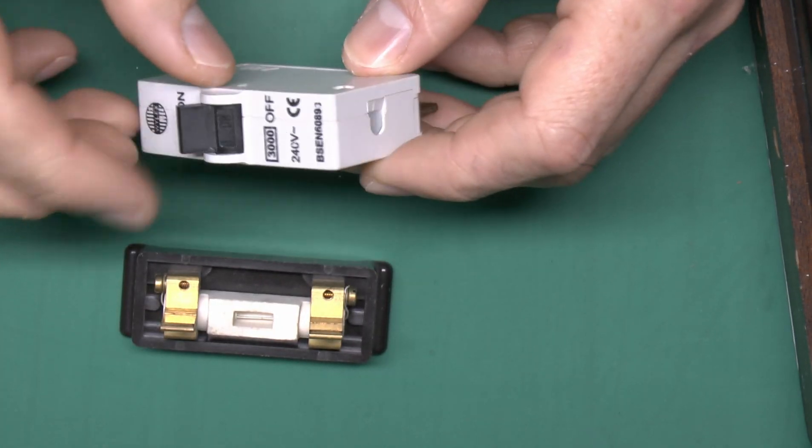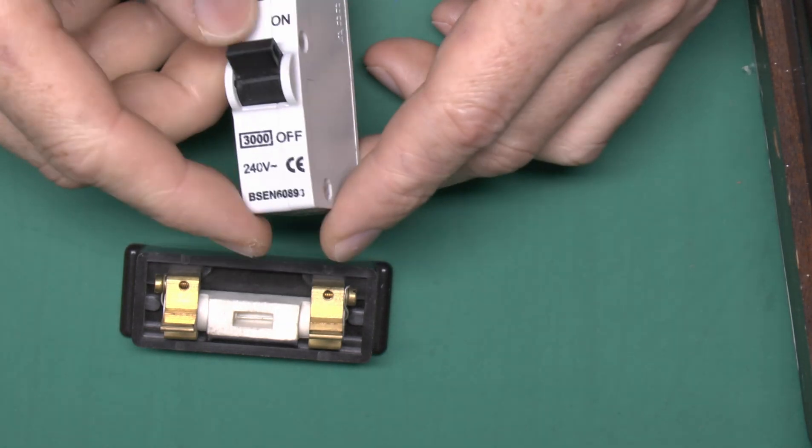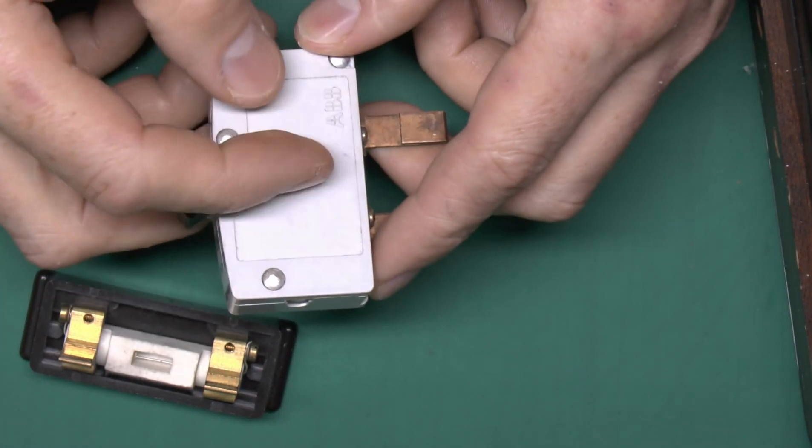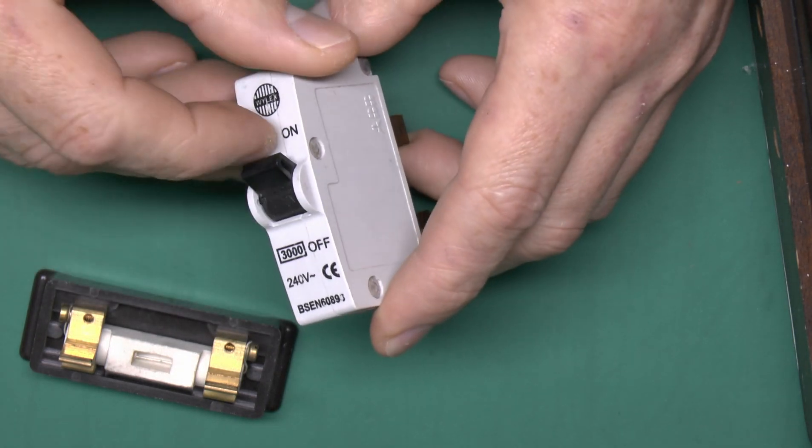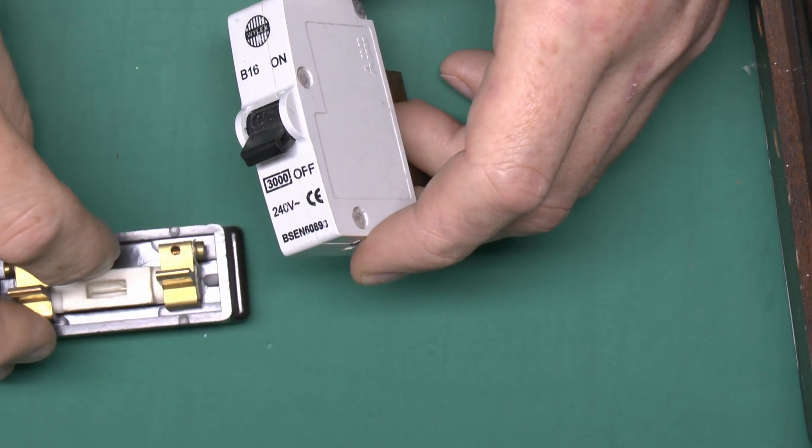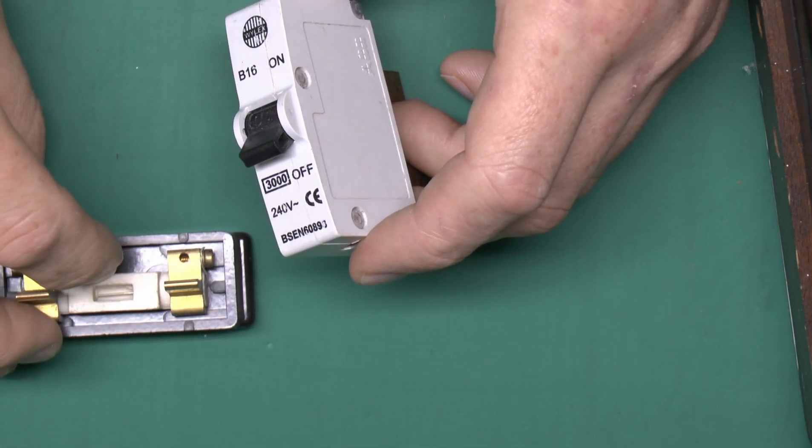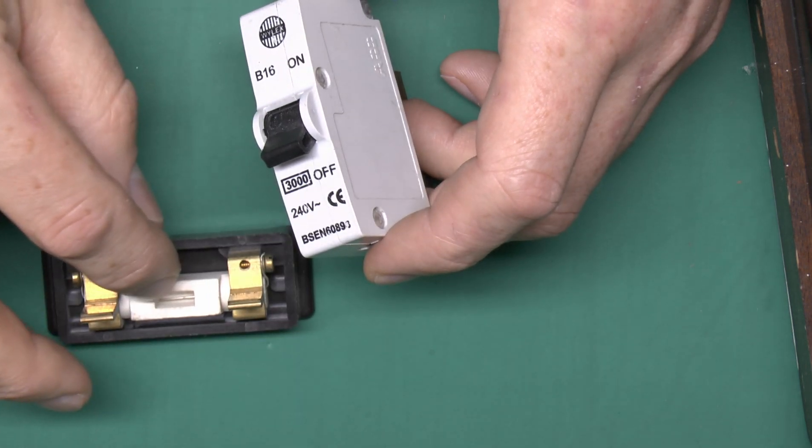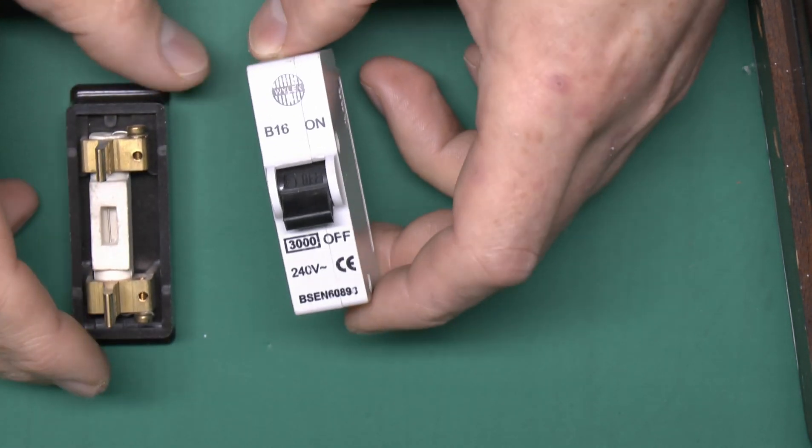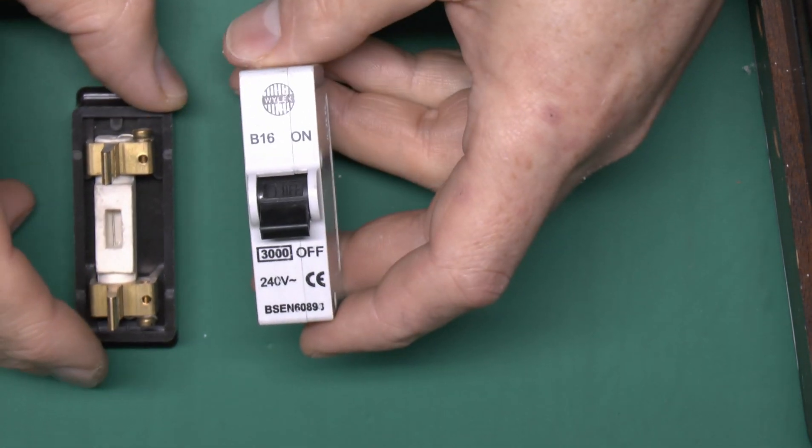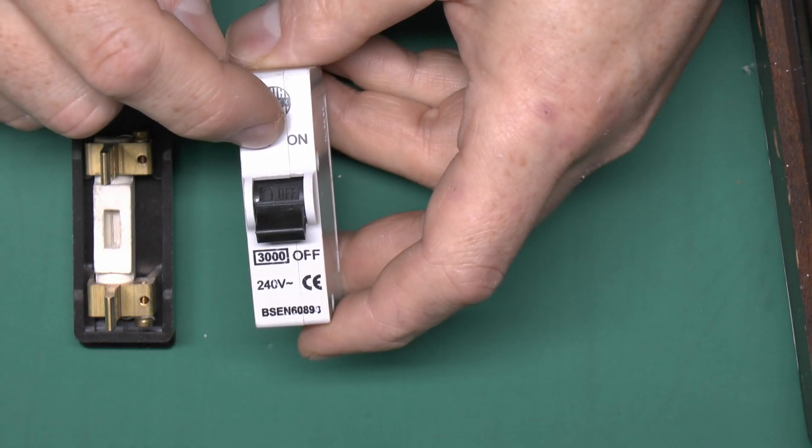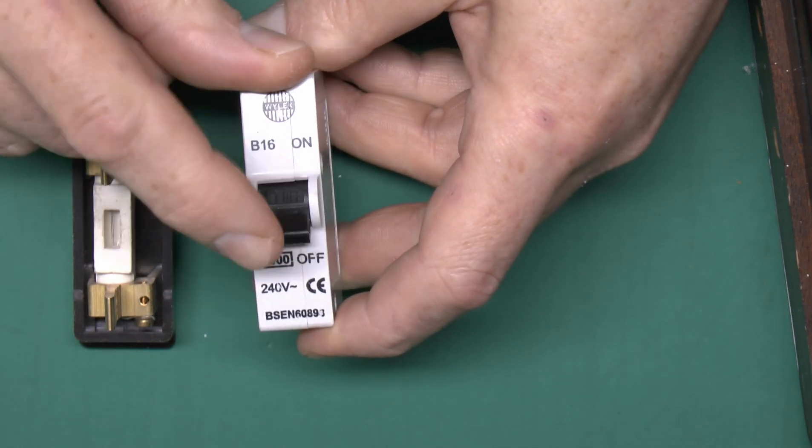These have two parts inside, there's a bimetallic strip and essentially as current passes through this heats up slightly and when it heats up to a certain degree it will cause the thing to trip off. Of course that's exactly the same as the fuse here which is just a piece of wire that heats up and obviously if the current is too large it heats up enough and it will melt through. So in that regard they're exactly the same and for short circuits where you're going to get a very substantial current flowing this has a magnetic coil inside and if the magnetic field reaches a certain level again that will cause the lever to trip off.